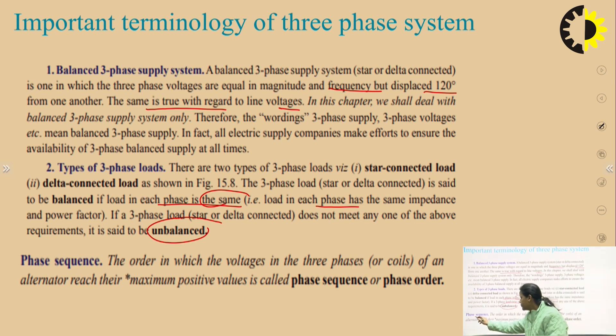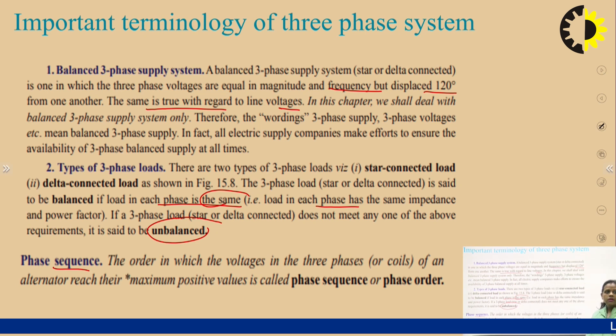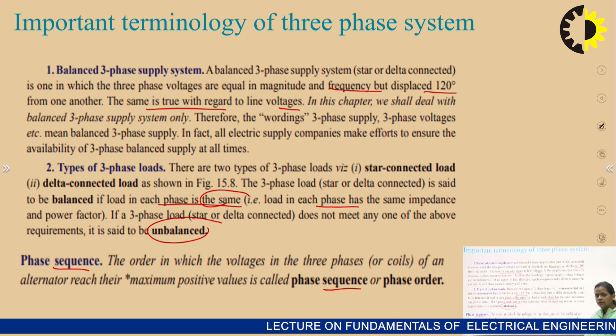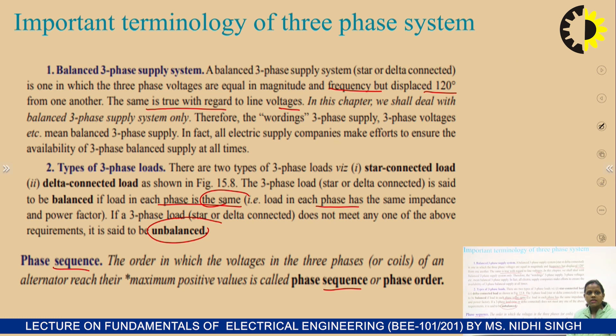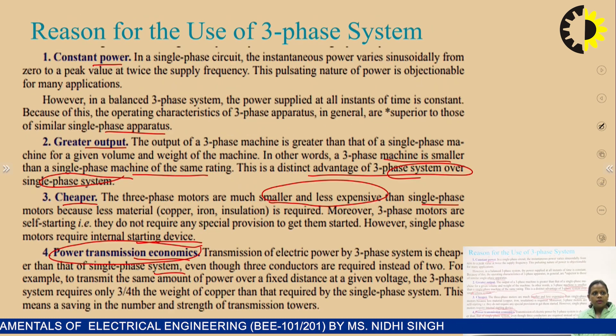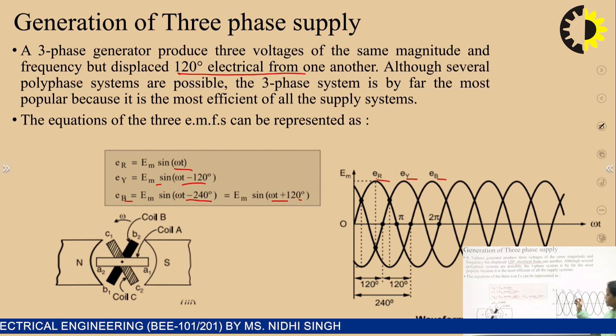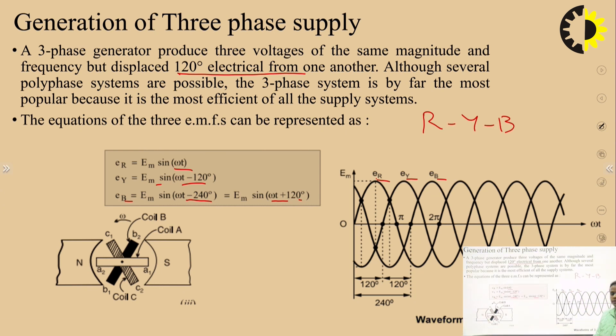The next important term is phase sequence. The order in which the voltages in the three phases of an alternator reach their maximum positive value is called phase sequence or phase order. Importantly, by changing the phase sequence we can change the direction of rotation of a motor. For the waveform shown, the phase sequence is R, Y, B — ER reaches its peak first, then EY, then EB.